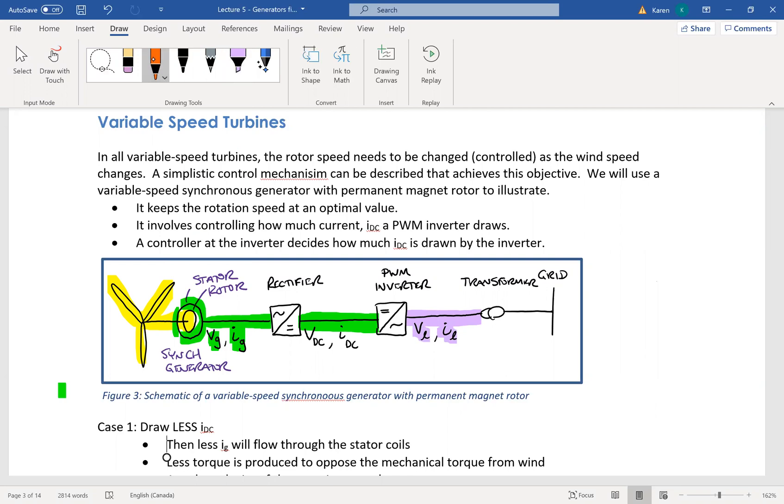And what I want to make note of here is that in this variable speed synchronous generator situation, it's a pulse width modulator inverter that actually does the control. So this is where the control happens and what it is controlling is it controls the DC current. So this is controlling your DC current.